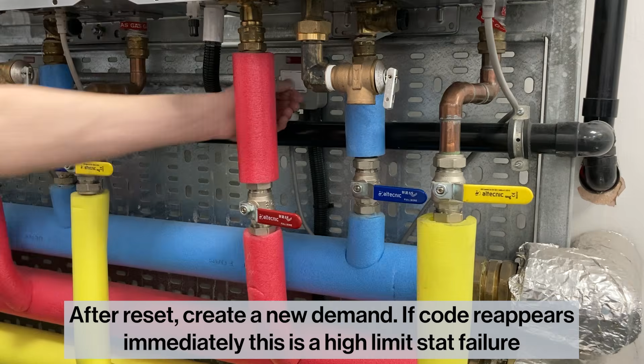After reset, create a new demand. If the code reappears immediately, this is a high-limit stat failure.